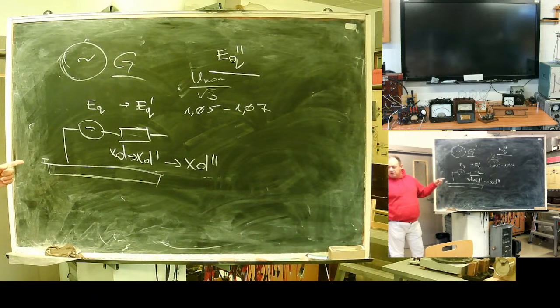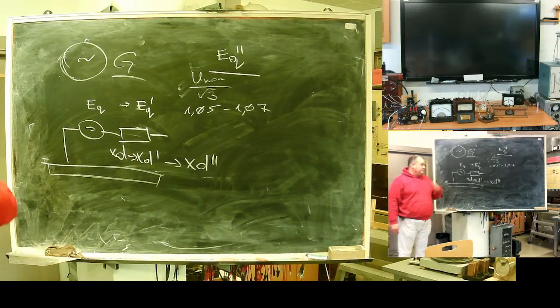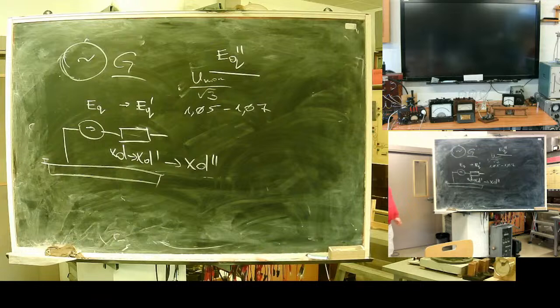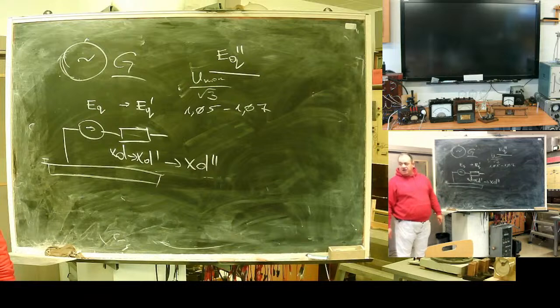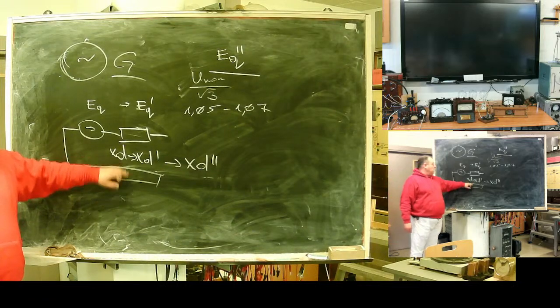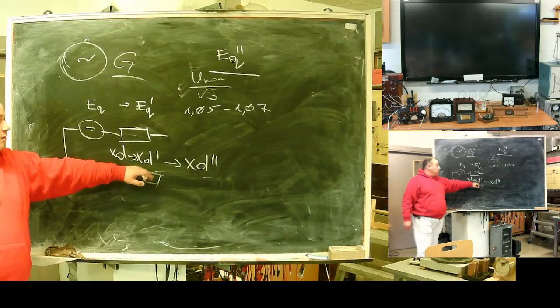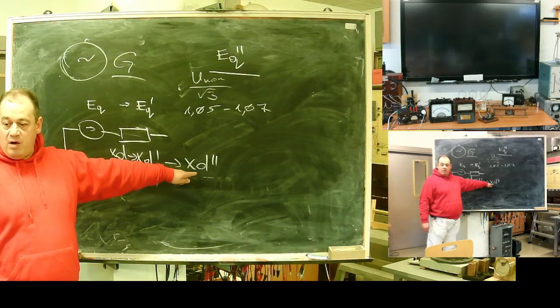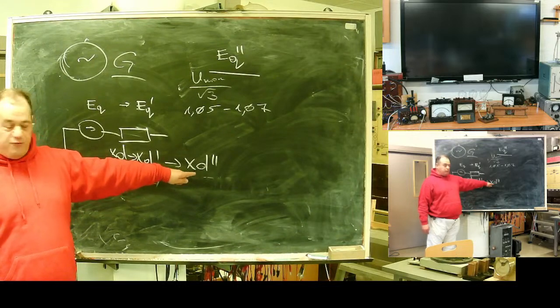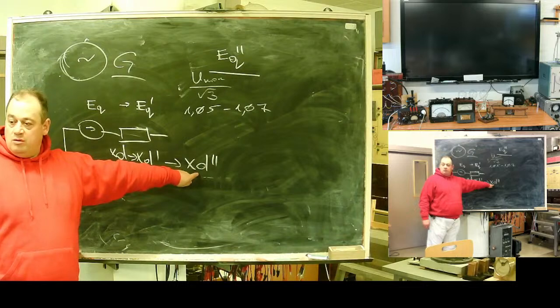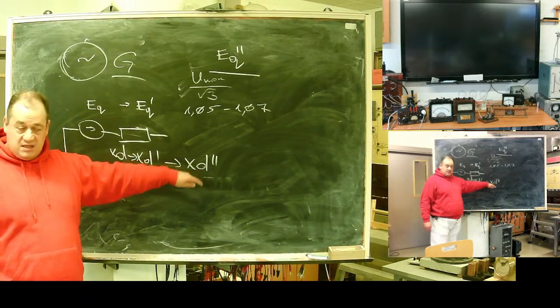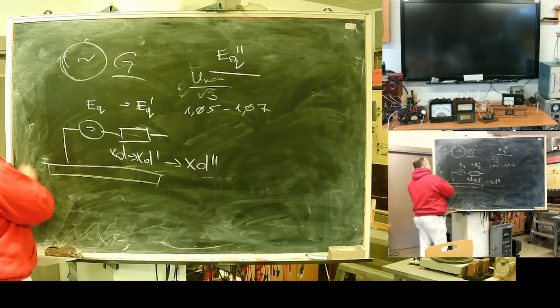At this moment I speak on stable or enforced regime. When you need three components, you will need to do all this mechanical calculation. Avoid this job, forward it to someone. But anyway, if the fault is far, or we are speaking on stable regime, longitudinal reactance. Fault near, transient: hydro power plant and the fault is near, for the first moment over-transient or super-transient reactance. This is for direct sequence.